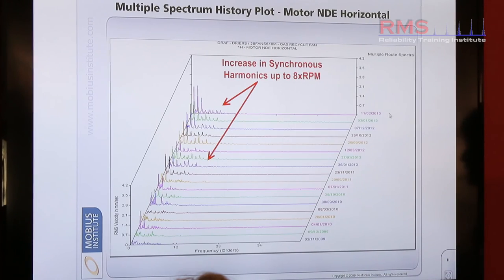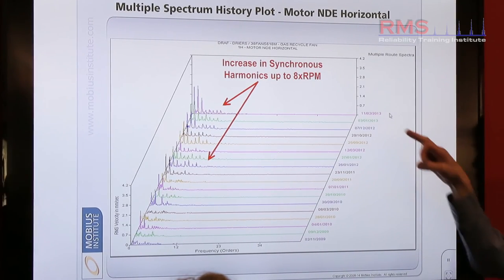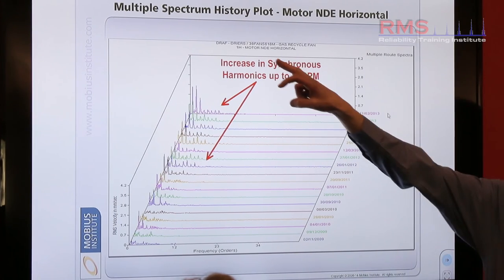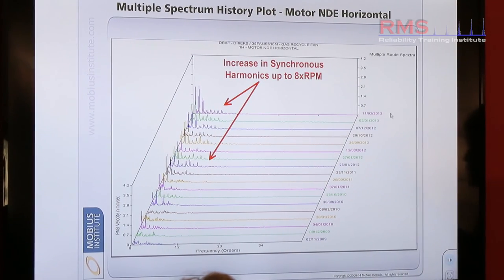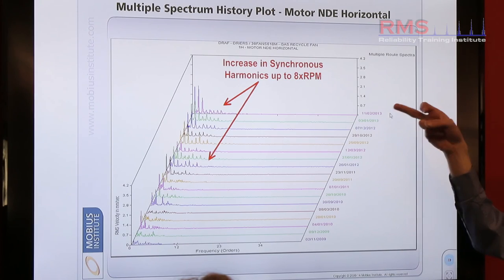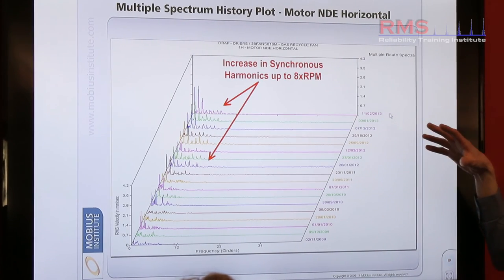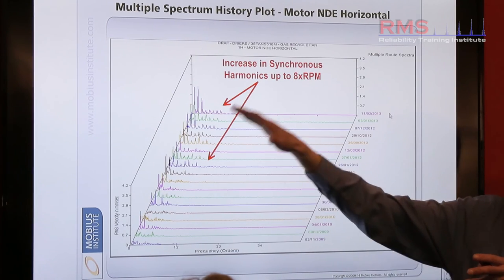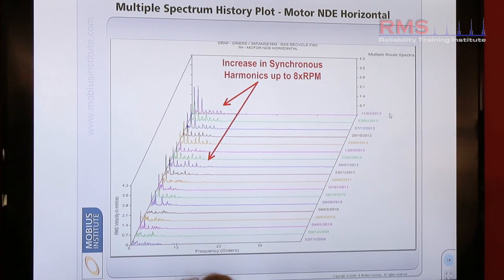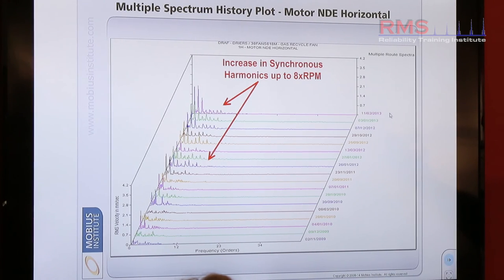Drilling down slightly deeper into the data, you can see the degradation. This is one particular point on the motor non-drive end. The most recent reading taken at the time when this was a problem is at the back. And you can see the visual picture there has changed, where you see obviously more activity at the back. Harmonics.